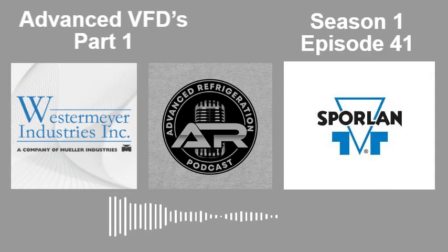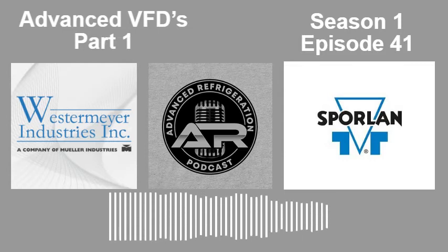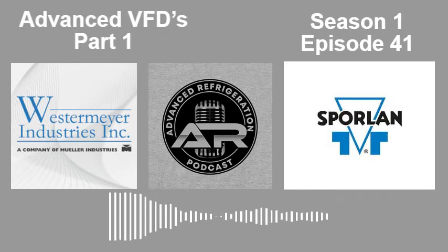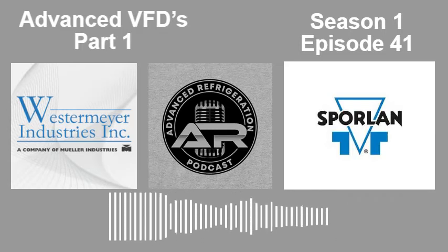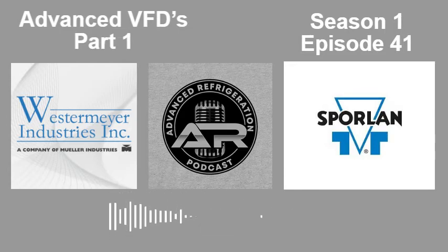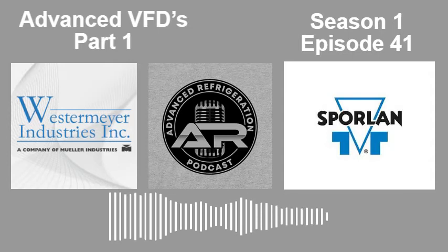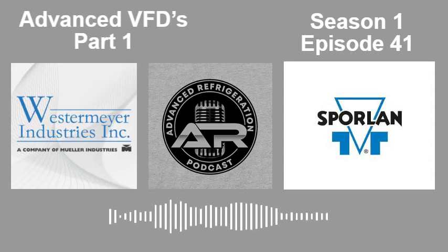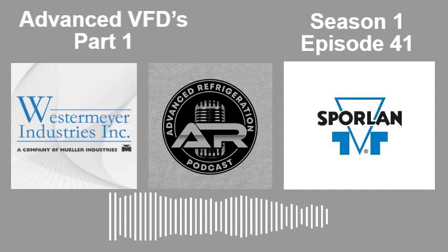Right on. And then lastly, we have BACnet, which just about everything is going to right now. Walmart made this big push a couple years ago. They wanted everything BACnet. BACnet is what they call an engineers' protocol. It's a big building protocol for HVAC stuff. Just about everything can be BACnet. It is basically a group of points you can read and write to.